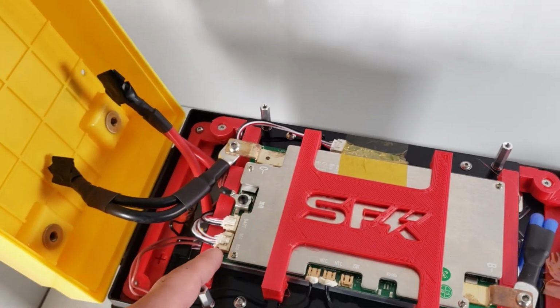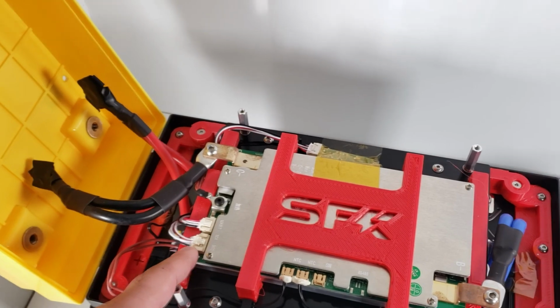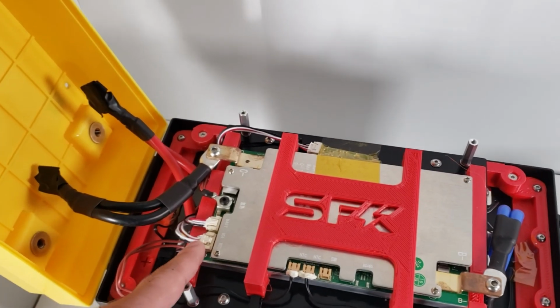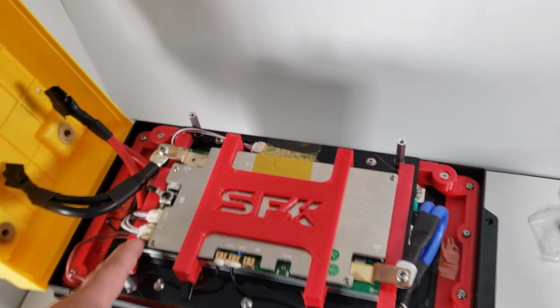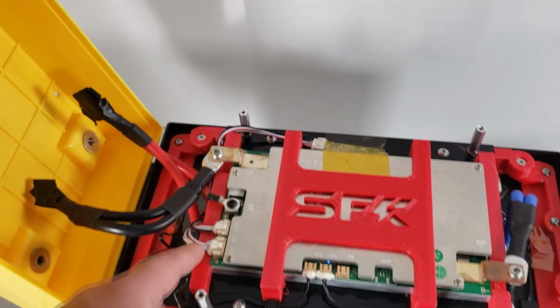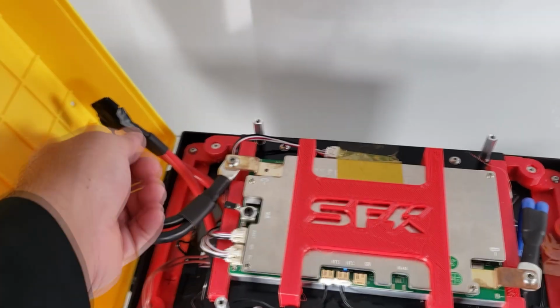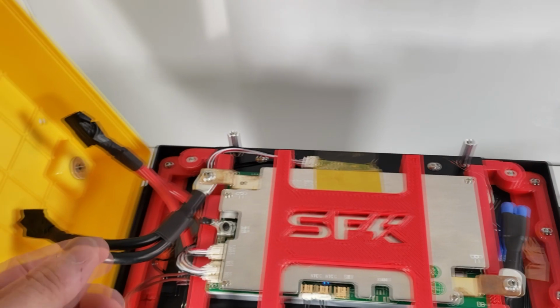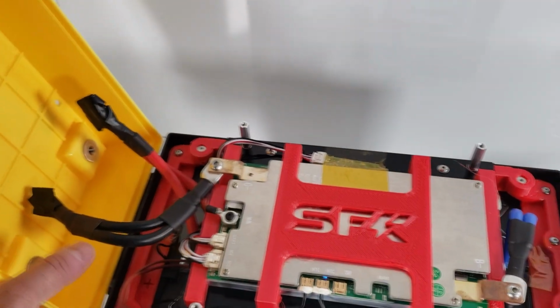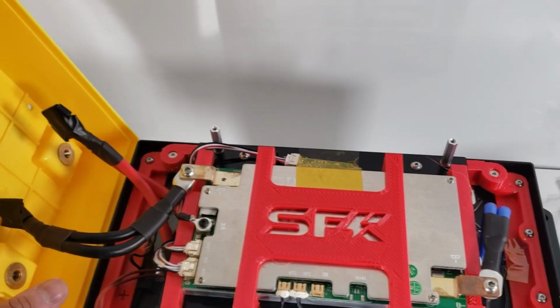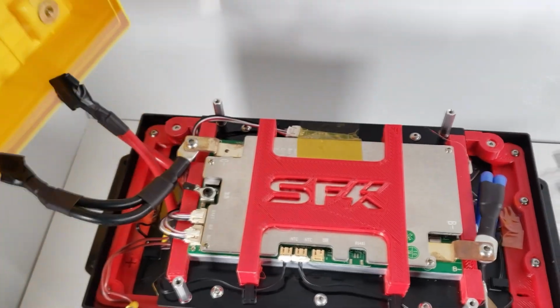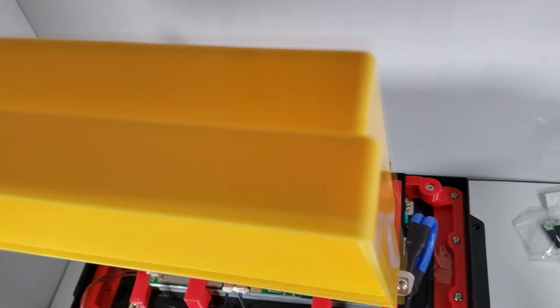You can optionally take this off, but we don't recommend disconnecting the battery BMS, because you will lose some settings, especially on the pre-built battery. So it's best to keep this connected and just wrap these with electrical tape. That should keep the battery isolated so there's no chance of an arc. Now we have taken the lid off, and we can begin the process to prepare this so we can install the external switch.